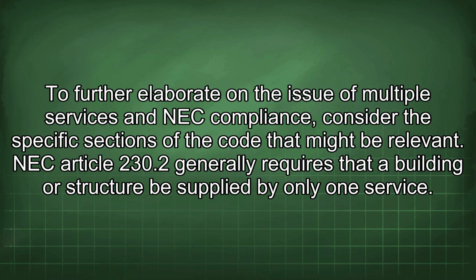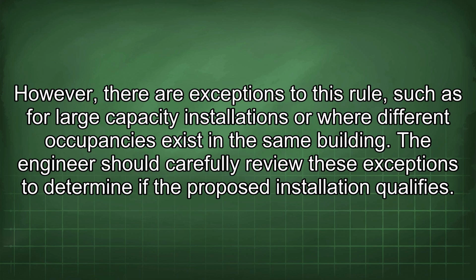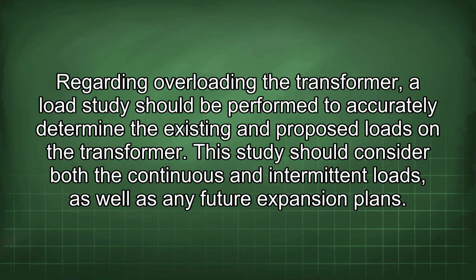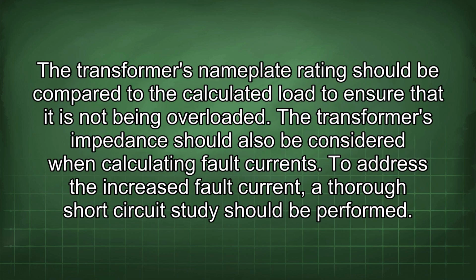To further elaborate on the issue of multiple services and NEC compliance, consider the specific sections of the code that might be relevant. NEC Article 230.2 generally requires that a building or structure be supplied by only one service. However, there are exceptions to this rule, such as for large capacity installations or where different occupancies exist in the same building. The engineer should carefully review these exceptions to determine if the proposed installation qualifies. Regarding overloading the transformer, a load study should be performed to accurately determine the existing and proposed loads on the transformer. This study should consider both the continuous and intermittent loads, as well as any future expansion plans. The transformer's nameplate rating should be compared to the calculated load to ensure that it is not being overloaded. The transformer's impedance should also be considered when calculating fault currents.